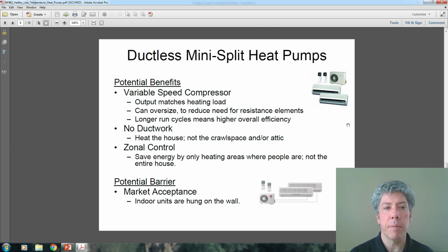There is another type that's becoming popular today. They're variable speed compressors. You might have seen these outside of commercial or some home installations. And the way these work is instead of having one centrally located expansion device, instead you have one outdoor compressor, which is an expensive component, but you have multiple indoor units. It's almost like registers you hang on the wall. And the nice thing about this is instead of having ductwork going throughout the home or the business or whatever, you can have small refrigerant lines because the refrigerant lines are actually very small by comparison to ductwork. It's easy to route them through a building.